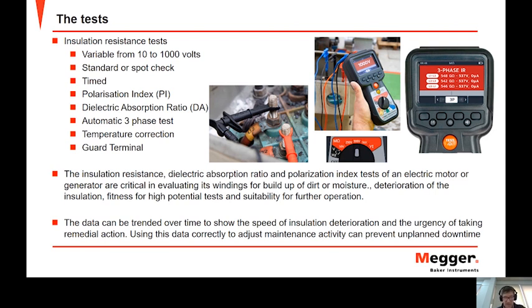So these tests are critical in evaluating a motor's winding for buildup of dirt or moisture, contamination, deterioration of the insulation, and whether or not the winding is able to take a high voltage or high potential test, and therefore is it suitable for further operation. The data can be trended over time to show the speed of insulation deterioration. But again, to have a meaningful trend, we need to temperature correct the IR values. Again, we'll look at that in due course.